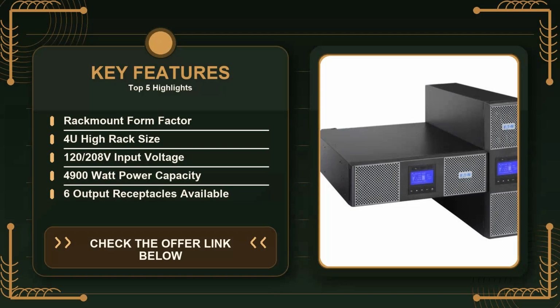Where the rubber meets the road are the practical weaknesses. The battery runtime, as mentioned, caps out at around 10 minutes at half load. If your workload is heavy, that window shrinks dramatically. And because the unit uses a sealed lead-acid battery, you'll need to replace the battery every 3 to 5 years to maintain that runtime. Battery replacement isn't a huge task, but it does mean you'll have a recurring expense that some users might not anticipate when they first see the price tag.